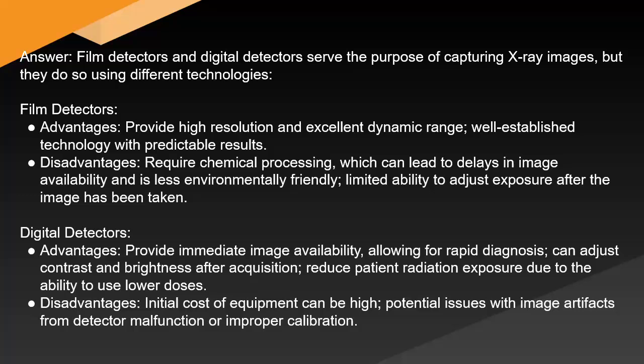Digital detectors' advantages: they provide immediate image availability, allowing for rapid diagnosis. You can adjust contrast and brightness after acquisition, and reduce patient radiation exposure due to the ability to use low doses. Disadvantages. Initial cost of equipment can be high. Potential issues with image artifacts from detector malfunction or improper calibration.